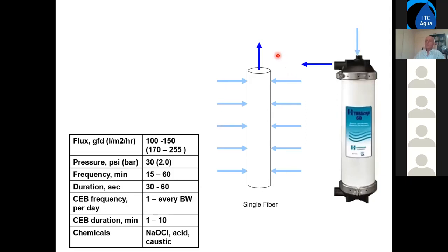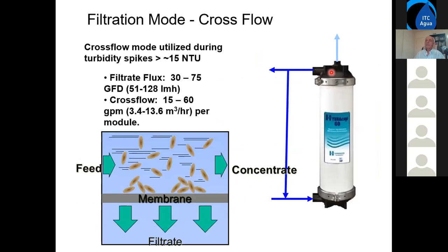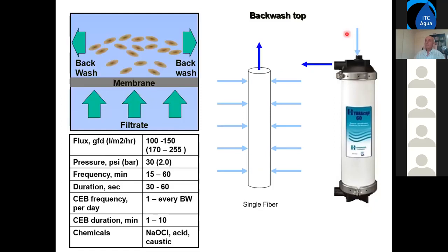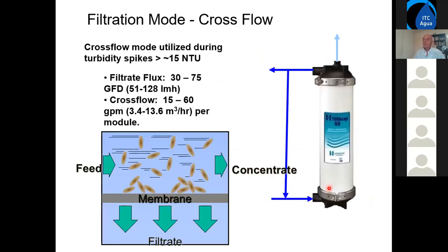Okay, in the backwash we're doing, first of all, we allow water to go from the top and then allow water to go from the bottom, and then go to the crossflow. Allowing water to leave only from the top, then only from the bottom, is to improve the backwash, because the capillary length is 1 meter. Usually the effectiveness comes from close to the port, which allows water to escape, and the other part is not so well backwashed. So we reverse this, close here, open here, and this way we get a more effective backwash. And then we do cross flow, letting just feed water flush for a very short time to sweep the foulant from the membrane surface.